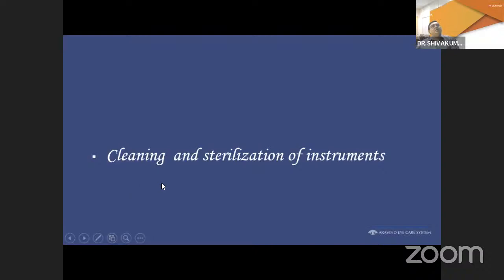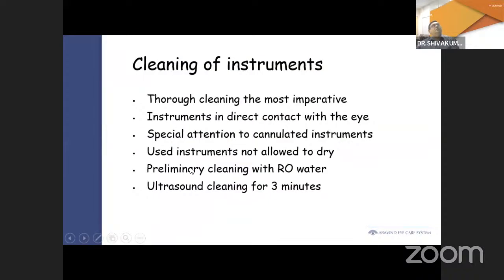Coming to the cleaning and sterilization of instruments, which is probably the most important part for prevention of endophthalmitis. It is imperative because these instruments come in direct contact with the eye, and special attention is to be given to the cannulated instruments. And these instruments which have been used should not be allowed to dry, because it is difficult to remove the organic material and the debris which stick to these instruments. So the preliminary cleaning should be done with RO water, and then should be subjected to ultrasound cleaning for 3 minutes, which helps to dislodge the debris and the organic material.